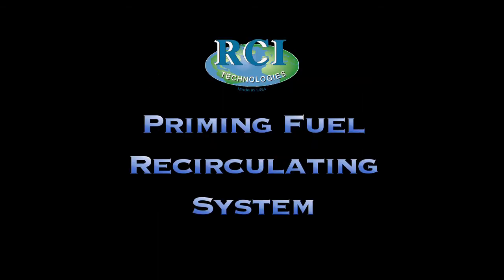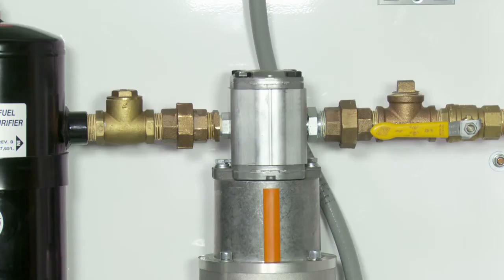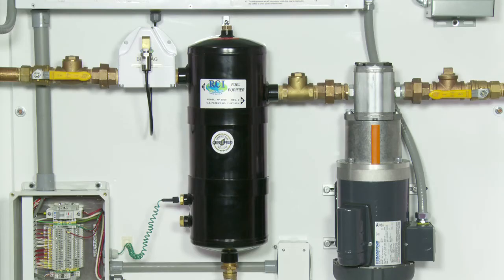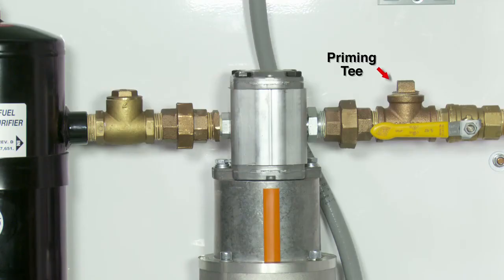Priming the fuel recirculating system. Prior to startup, you must first prime your system. The pump head of the FRS 660 unit is shipped from the factory filled with number 2 diesel to facilitate system priming. But remember, this will not eliminate the need to prime the system at the pump. The FRS 660 is primed by using the priming tee on the inlet side of the pump.